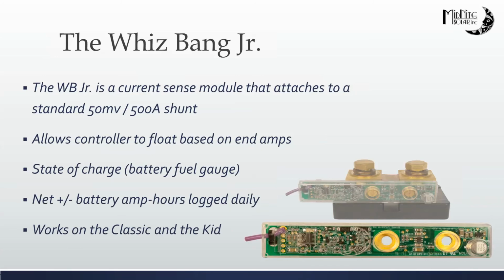And with that, we're able to do things like an accurate state of charge, because now the charge controller is doing it. It knows the battery's temperature and can adjust for that. It knows when it went to float, so it can recalibrate to 100%. If any of you have used Trimetrics, you'll know that if you don't get it perfect, over time they'll keep dropping in percentage, and the battery can be completely full and it might say 10%. So this is kind of eliminated by letting the charge controller do that work. That's a really nice way of doing it.